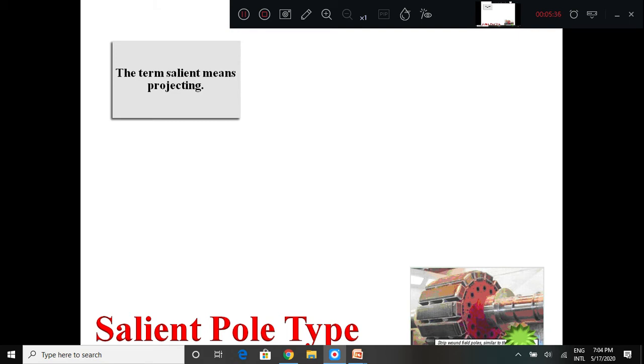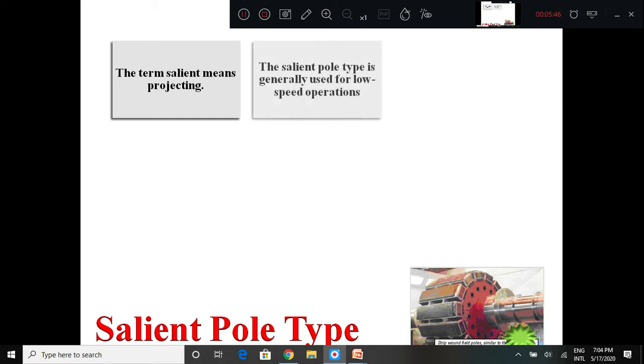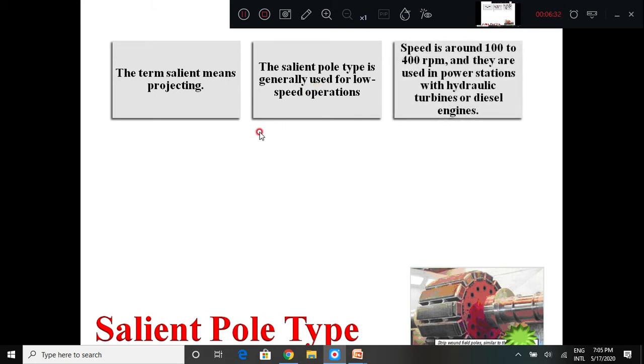In the salient pole type, the term 'salient' means projecting - the poles are projected. The salient pole type is generally used for low speed operation. Because the salient poles are projecting and attached to the rotor, if rotated at very high speed there is centrifugal force exerted, so these salient pole alternators are designed for very low speed operation. Usually the speed is around 100 to 400 RPM. These are driven by hydraulic turbines or diesel engines.